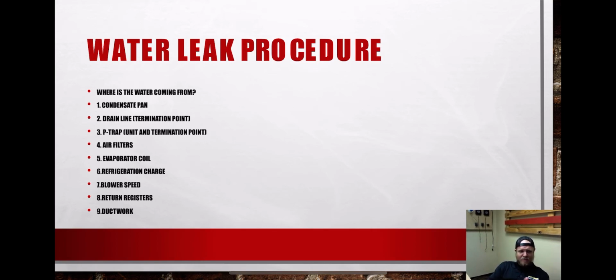Inspect your P-trap, unit, and your termination point. There could be a P-trap at the termination point. A lot of smaller single unit stores, they hit the P-trap on the employee bathroom sink. You want to look at that. If you blow that out, you're blowing stuff straight out of a P-trap into somebody's face if they're standing at the sink. That is the worst thing, absolute worst thing that could happen. So same thing, don't blow that out unless you know where it goes.